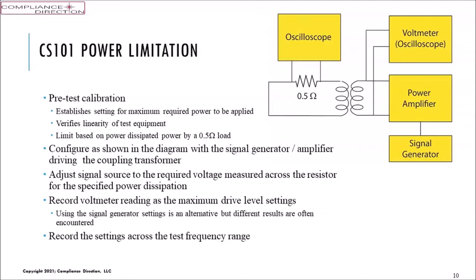So the cables could have a problem with them. We could have a long cable installed on the current probe because we want to reach a long distance here, and we see a reflected waveform from the cable length. We forgot to get rid of that T connector, and we see a standing wave problem on the cable when it's fairly long. At these frequencies for CS101, it would take a fairly long cable to cause that event, but I've seen it happen where the T connector wasn't removed at the higher frequency calibrations, and the T and the cable that was attached over to the oscilloscope was a little bit long, and got a standing wave issue with high SWR. So many things could be there, but that's what we have to do to figure out what's wrong with this, make the corrections, and then redo the calibrations.